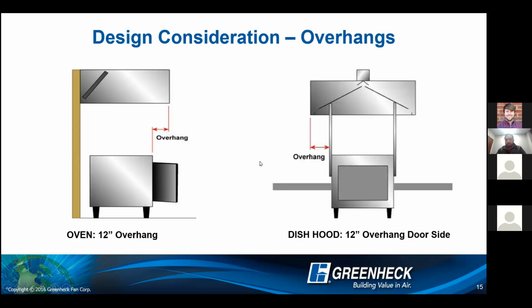Same concept for dish hoods. When these commercial dishwashers are running, the side doors are typically down, so heat is building up and condensate is building up. Then when they open, that escapes rapidly. If you only have 6 inches of overhang, there's high potential for that to escape the capture area. So I would recommend a 12-inch overhang from any door side of a dishwasher.